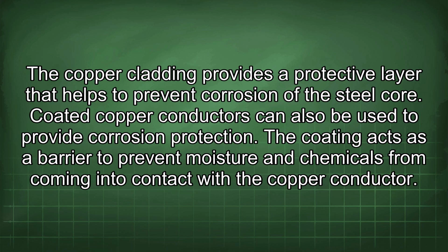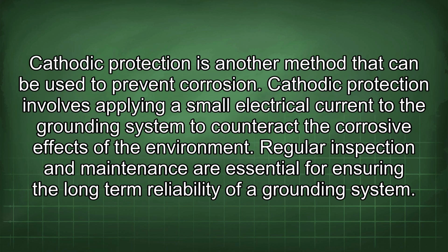Coated copper conductors can also be used to provide corrosion protection. The coating acts as a barrier to prevent moisture and chemicals from coming into contact with the copper conductor. Cathodic protection is another method that can be used to prevent corrosion. Cathodic protection involves applying a small electrical current to the grounding system to counteract the corrosive effects of the environment.